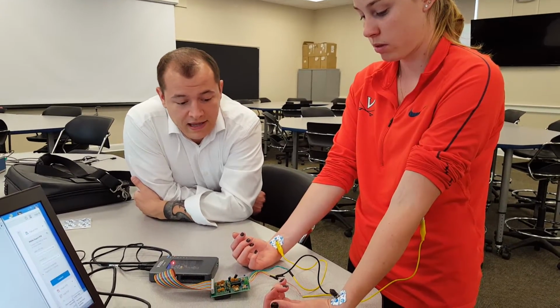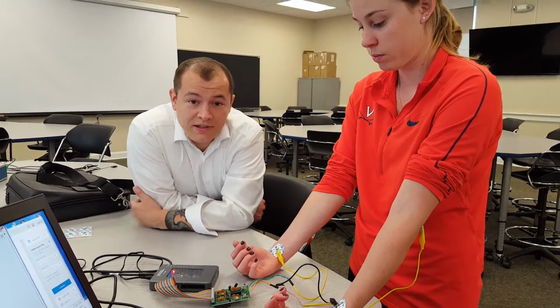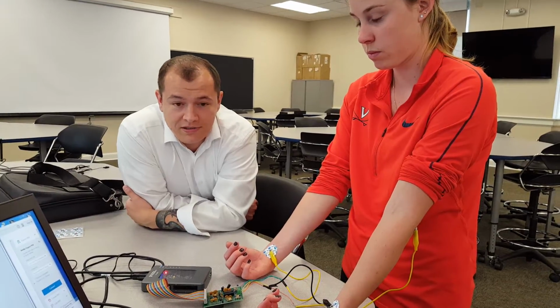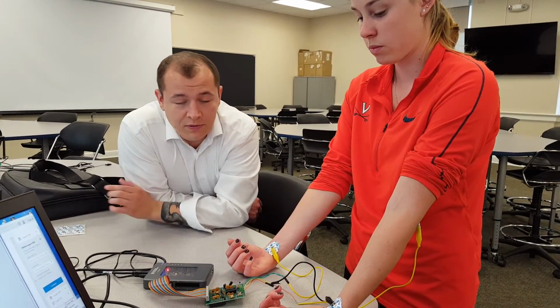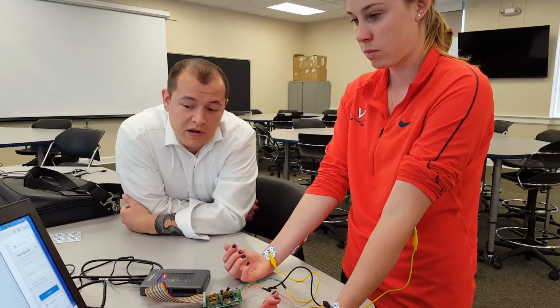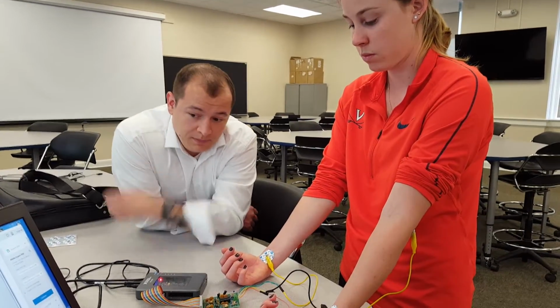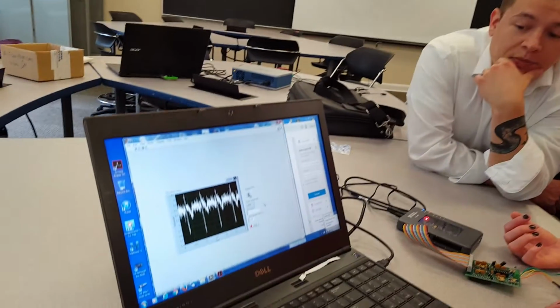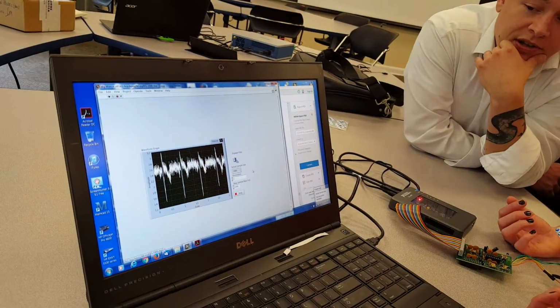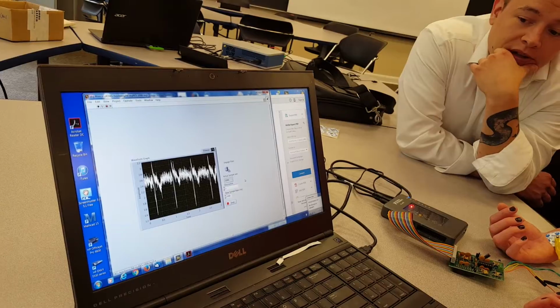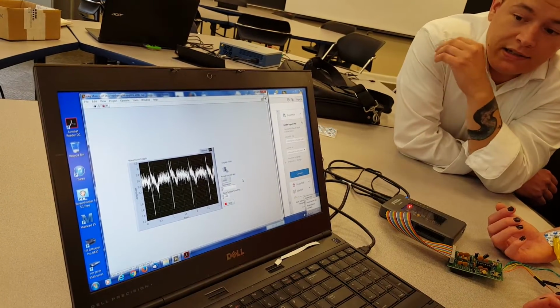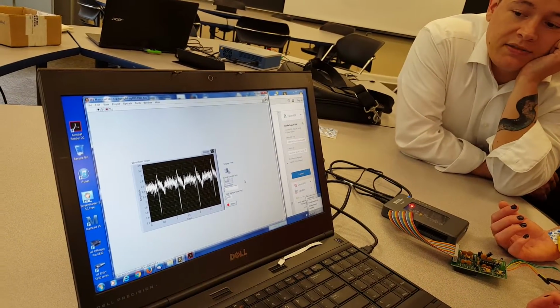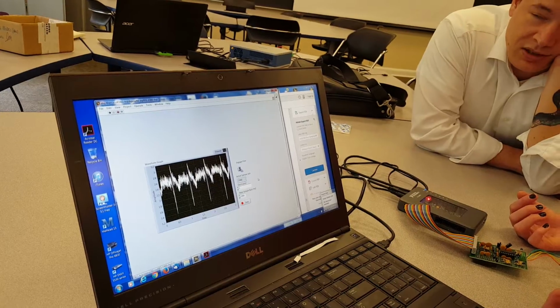And then after that, most of our sampling and filtering can be done digitally, or we can zero in the EKG to wherever we want. When we're actually doing the sampling, though, that means that we have to sample at about 1,000 hertz in order to avoid any aliasing in our signal, overlap in as far as digitally.